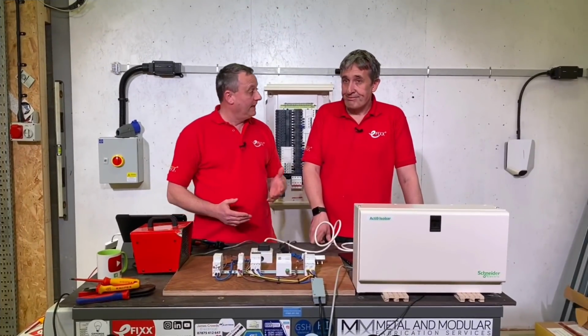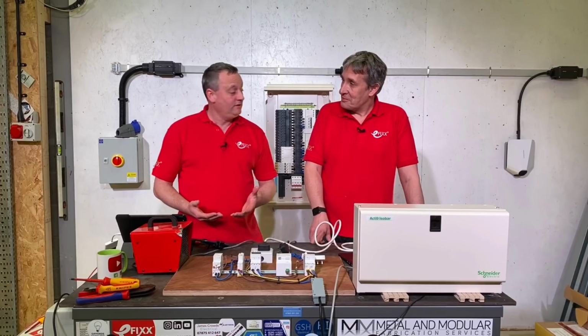As we bring that lighting level down, we expect to see the power fall, wouldn't we? Yeah, and power factor is normally quoted on LED products at full power, so you can see the power factor starting to change as well. Carry on dimming it down to its bottom end. Yeah, that's down at 44 watts, and you can see the power factor's changed there too. It just seems too easy.